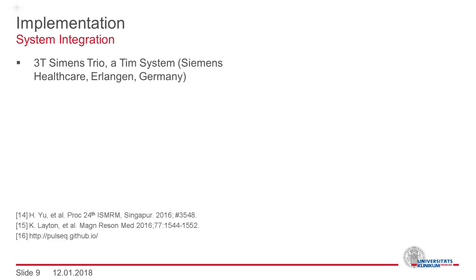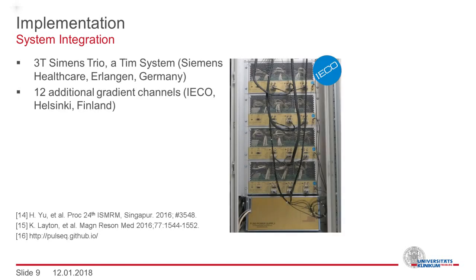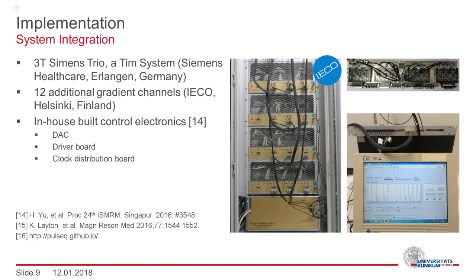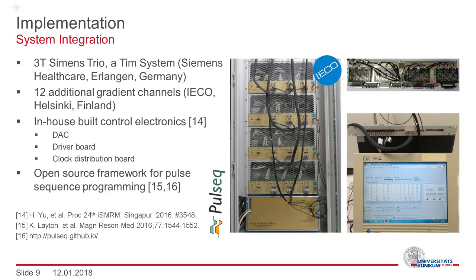The coil was integrated into our 3T scanner environment. We used 12 additional gradient channels to control our coil. The gradient amplifiers are controlled by in-house built electronics, which consists of a digital to analog converter, a driver board, and a clock distribution board. Within this project, the open source framework Pulseq was developed, which allows for really simple pulse sequence programming. You can find more information in the MRM paper or download the source code on GitHub. Within this framework, we can control the scanner and the additional components in a really simple way.